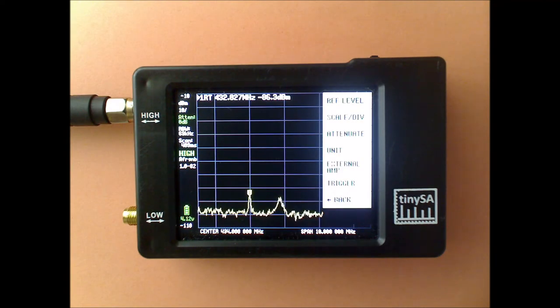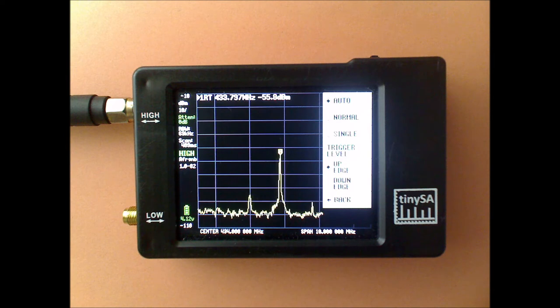The last item in the level menu is the trigger submenu. And to demonstrate that, I've switched to the high mode, center frequency 434 megahertz, 10 megahertz span. And I'm interested here to capture the frequency of some signals that are very briefly present.